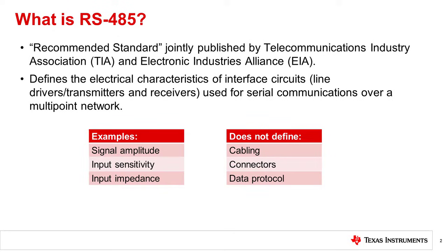The standard is intended to be referenced as the physical layer for higher level standards, such as DLT645, DMX512, Modbus, and others, and is used widely in industrial applications for its robust electrical characteristics. RS-485 allows for serial communication across a multipoint network. Some examples include the minimum required signal amplitude generated from the transmitter side, the input sensitivity of the receiver, and the input impedance of the receiver. Cabling, connectors, and data protocol are not defined in the standard, allowing system designers to increase flexibility.